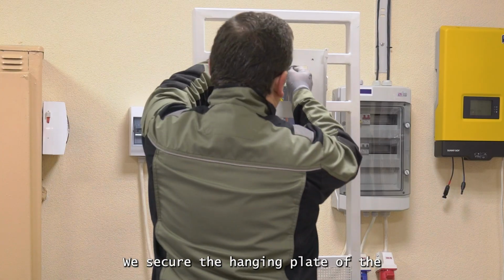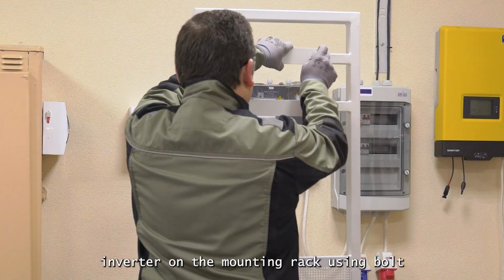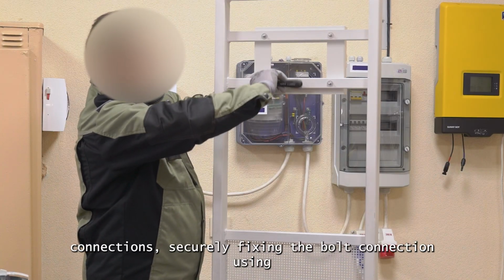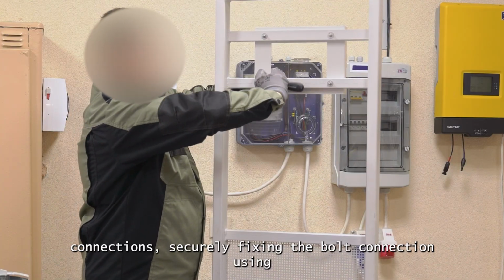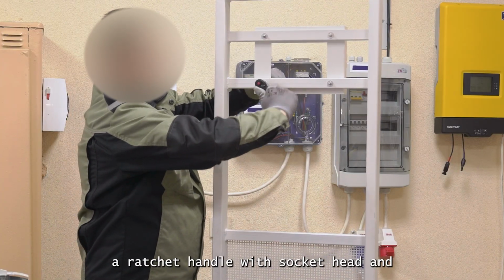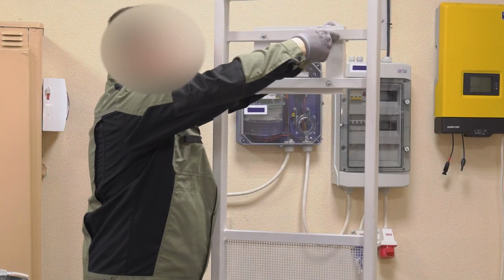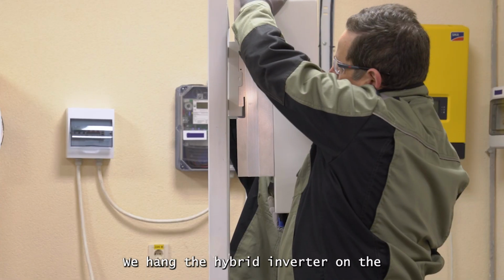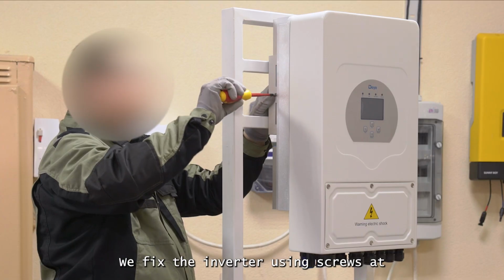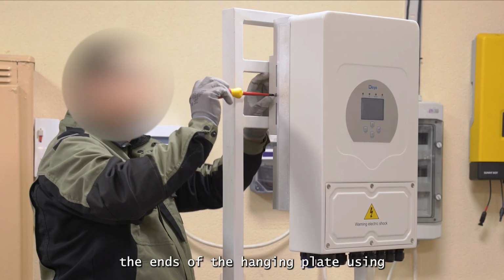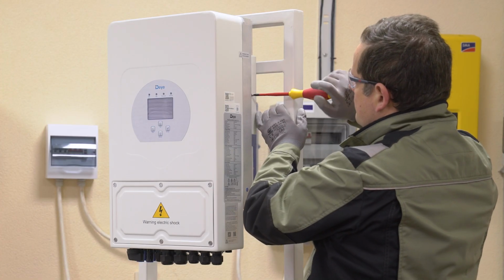We secure the hanging plate of the inverter on the mounting rack using bolt connections, securely fixing the bolt connection using a ratchet handle with socket head and combination wrench. We hang the hybrid inverter on the hanging plate. We fix the inverter using screws at the ends of the hanging plate using a screwdriver.